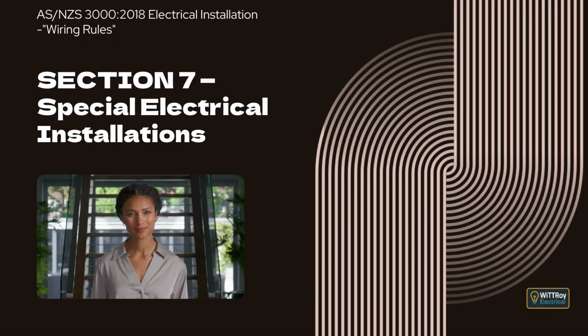Clause 7.2.5.5, Pump rooms for fire pumps and fire pump control equipment. This clause explains that in rooms used mainly to house fire pumps, lighting equipment and socket outlets may be supplied as a final subcircuit from the pump supply, provided that the circuit is protected against overcurrent, protected by an RCD not exceeding 30 mA, and that the wiring system between the pump circuit and the final subcircuit protective device meets the current carrying capacity, installation, type and segregation requirements of the relevant clauses. An exception is explained for lighting and socket outlets in pump rooms where certain wiring system requirements do not need to apply.